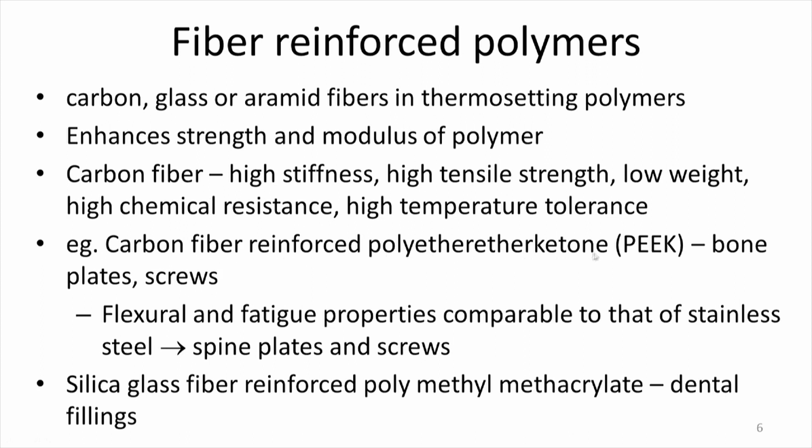Carbon reinforced polyether ether ketone, for bone plate screws. Flexural and fatigue properties comparable to that of stainless steel, for spine plates and screws. Whereas this polymer may be very light. So, by adding this carbon we are getting very good flexural and fatigue properties equivalent to stainless steel.